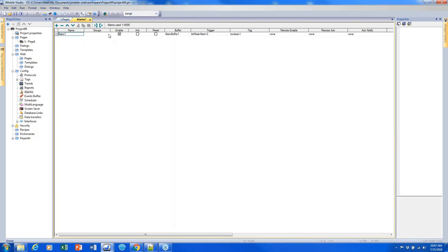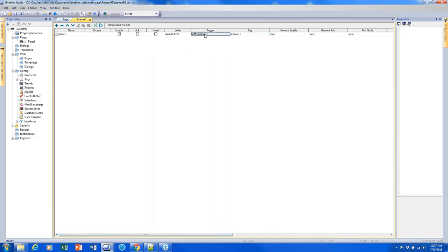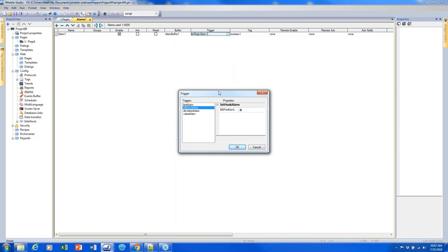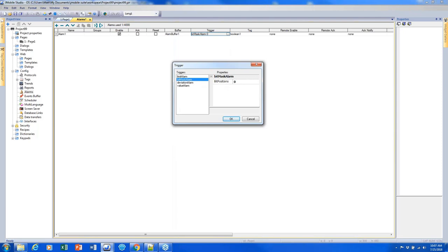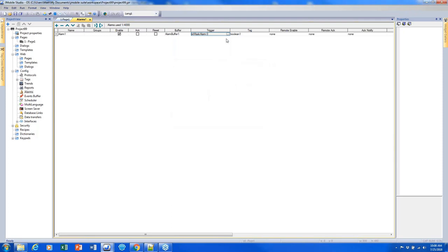To create a new alarm, just click this plus sign. We can give it a name and put them in groups. The important things we'll be paying most attention to are the trigger, the tag, and the action. I'll click in this cell under trigger and click the square to edit it. By default, it gave us a bit mask alarm, which will throw the alarm whenever the bit at this position is a one value.